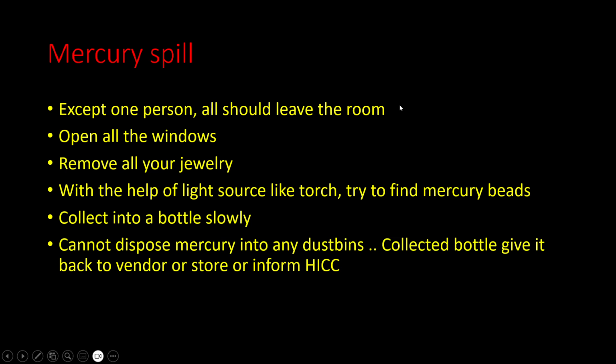Only one person should remain in the room, all other people should leave. Try to open all the windows so that the air becomes more and more diluted. If you are going to handle the mercury spill, remove all your jewelry. That is very important, because mercury reacts with gold jewelry and will totally destroy it. For that reason, you have to remove all the jewelry. Wear the complete PPE.